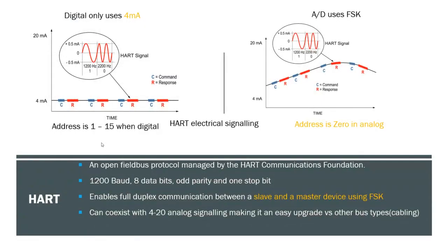This is the standard manufacturers use to ensure compatibility. For example, in HART, which is an open field bus protocol managed by HART, it tells us that we use frequency shift keying, varying the frequency or frequency shift between 1200 and 2200 hertz. It also tells us that when doing digital-only signaling, we have to have an address between 1 and 15, and when we want to use analog and digital, or the pure analog or hybrid style with HART, the address has to be zero.